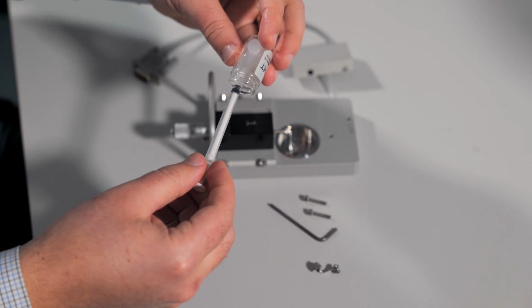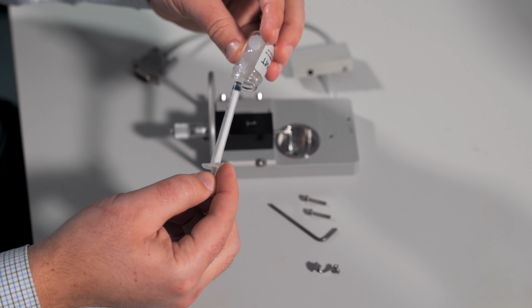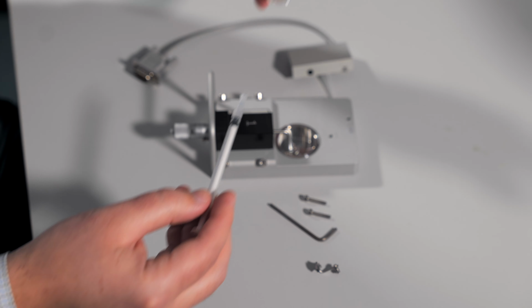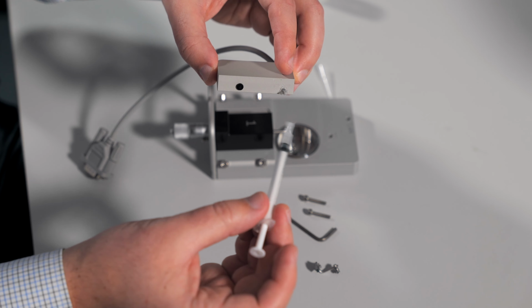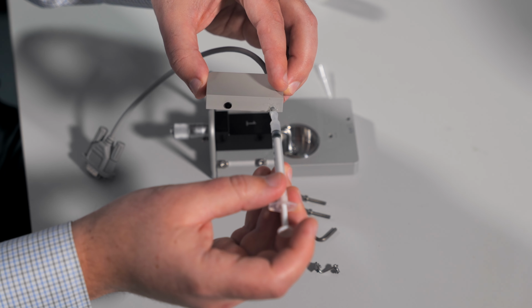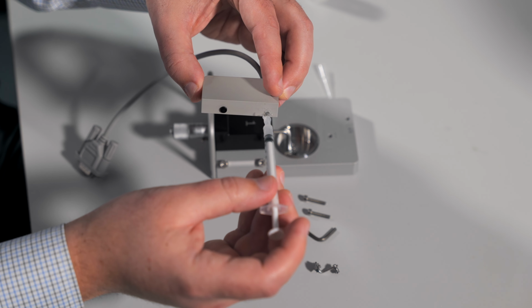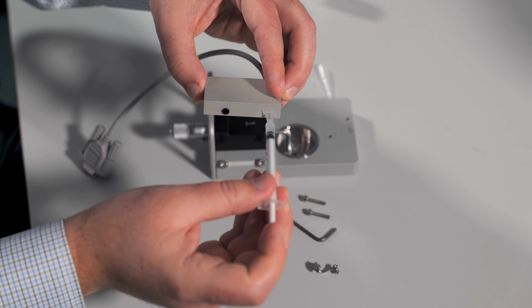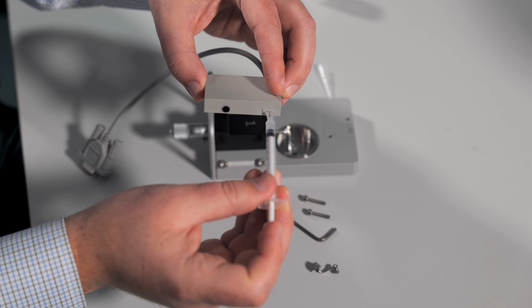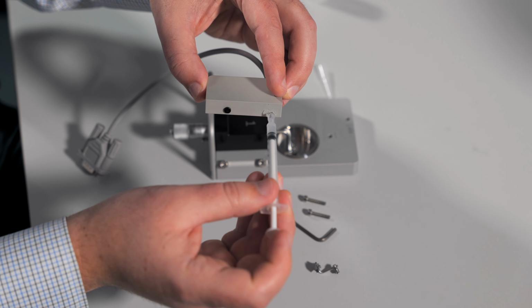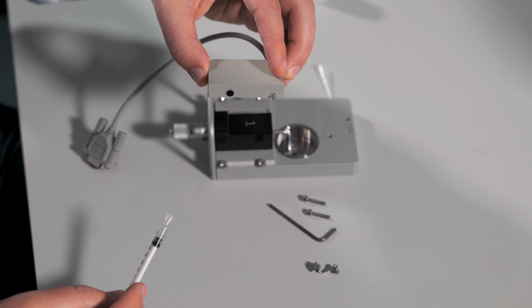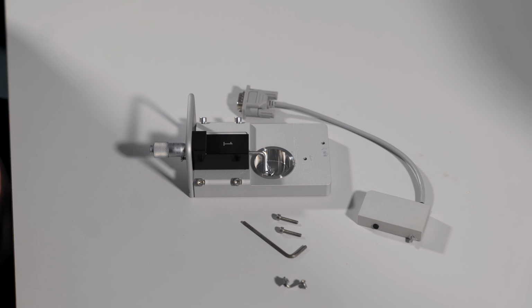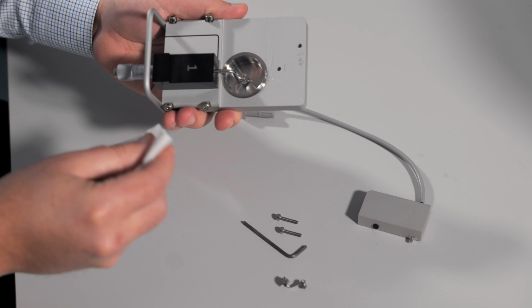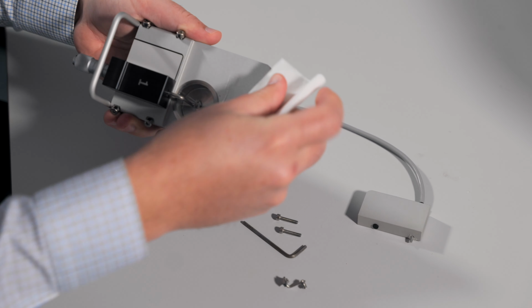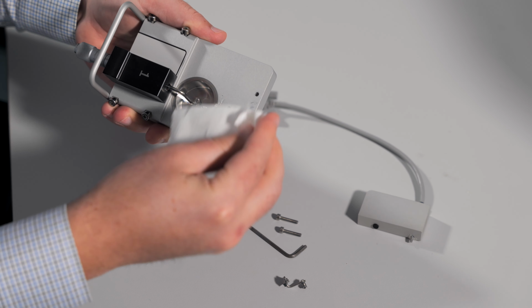Draw up some grease into the syringe tip. You can place the tip of the transducer arm into the syringe and apply some grease. You do need to be careful here so you do not damage the replacement transducer. It's a good idea to remove any of the old grease. You can take a Kimwipe and wipe that away.